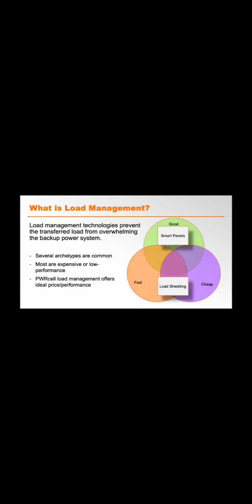Another popular but low-tech form of load management is called load shedding. Load shedding is usually achieved using low voltage relays. This is kind of a more DIY approach to load management. Basically what happens is when the grid goes down, relays open and loads are shed. That's it. They don't turn back on until the grid comes back. This is a little bit better than a sub panel, but it's not much better. You don't have a separate panel, but you're not getting those loads at any time during the outage. And there's no intelligence controlling how they go off. Just the binary: is the grid on or is the grid off?